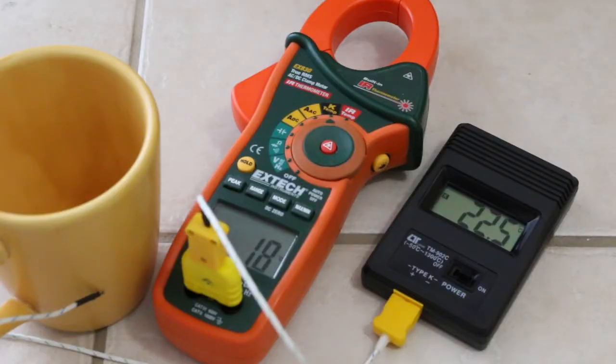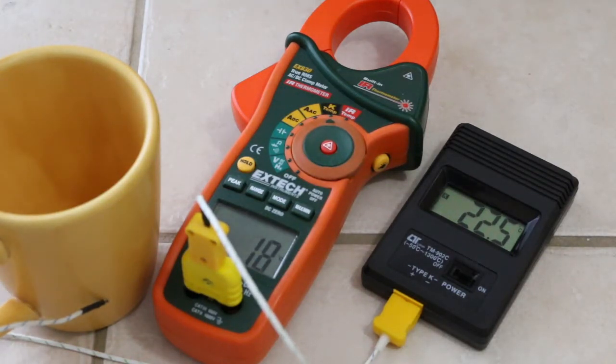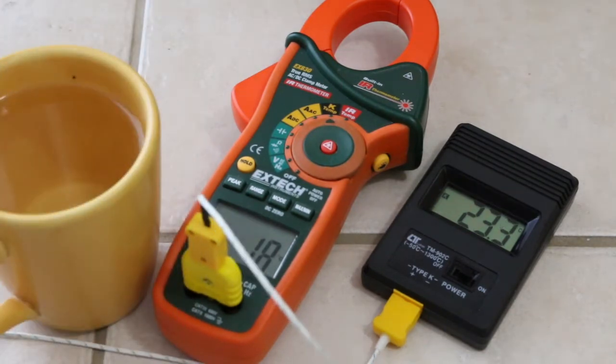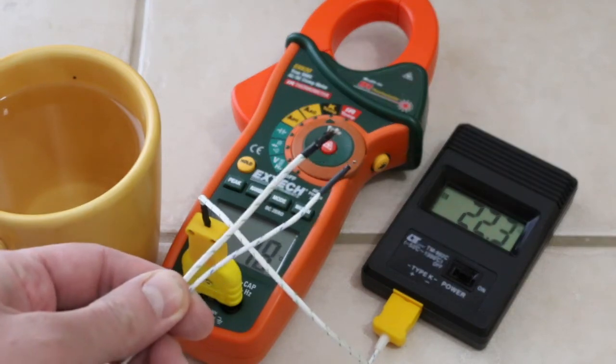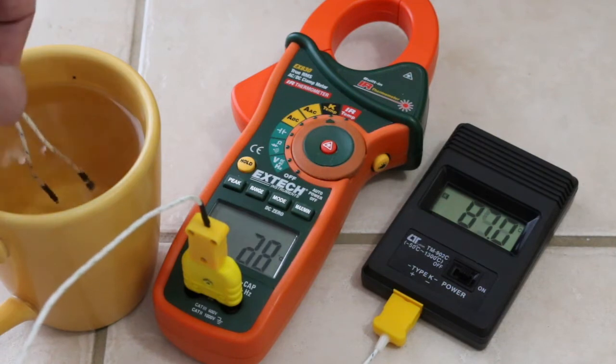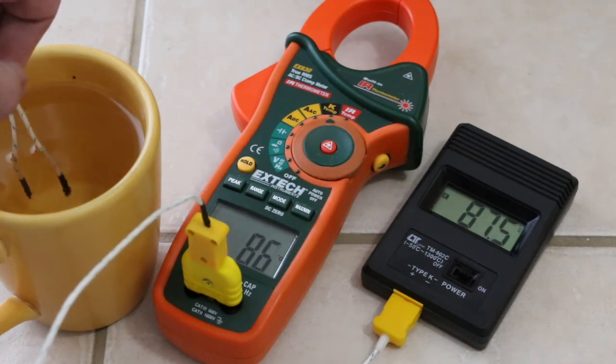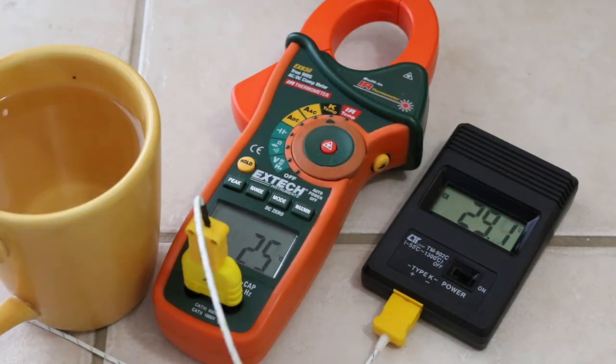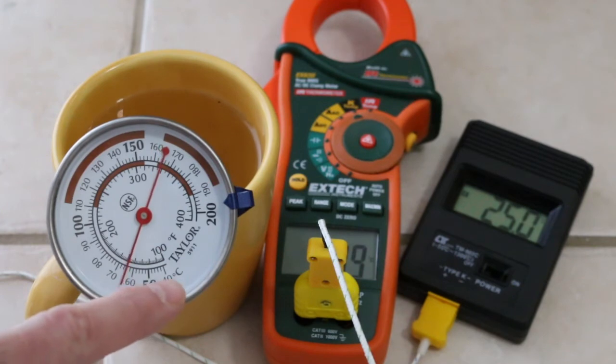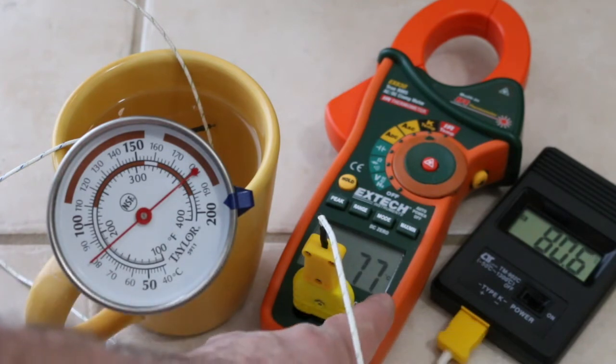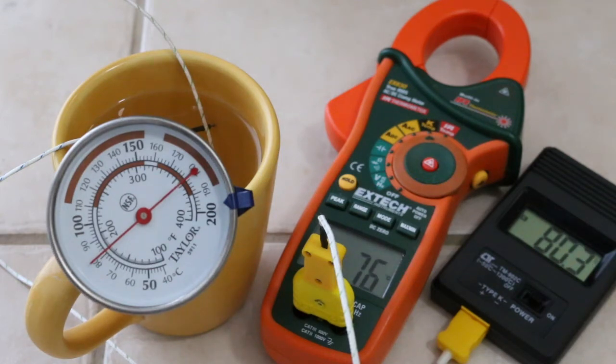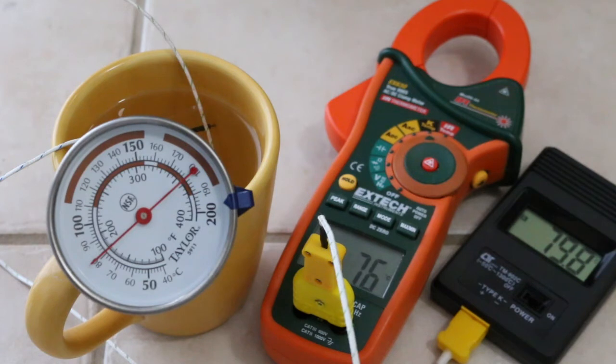Time to test these thermocouples using boiling water or close to it. The room temperature in here is closer to 23 degrees. This one says 18 but it's always been a bit off. So both probes at the same time in almost boiling water. They both go up 88 degrees, 86 degrees, 85. So what is the analog temperature of the water? Looking at the lower degrees Celsius scale, it's rising up. And we have 81 on the digital thermometer, 77 on the multimeter with thermometer interface. Overall that's reasonable. And I'm still surprised at how the cheap thermometer for a couple of dollars seems to be holding up across temperature ranges.